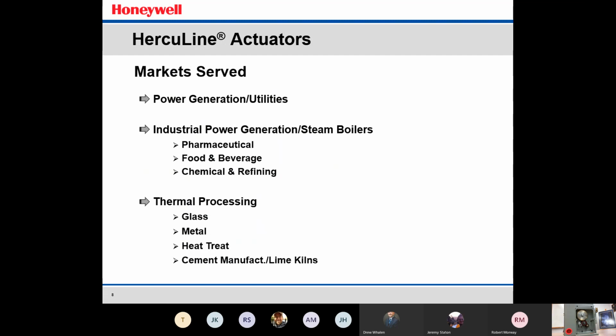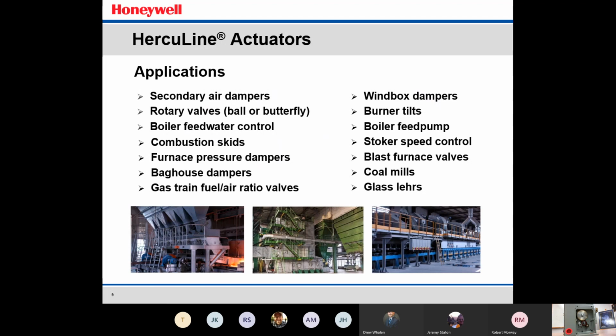Other applications inside these facilities that I mentioned on the previous slide: secondary air dampers, rotary valves, boiler feed water, combustion skids. Combustion skids are supplied to heat treat, steel, glass. In the glass industry, these 10260s are used pretty widely among a lot of the leading glass manufacturers in the U.S. So typically, if you walk into a glass plant, you'll see these on the combustion skids. Furnace pressure dampers. So this is your draft pressure control that needs very, very finite control to either the furnace or the heat treat oven, where you're controlling a draft pressure that might be down into the 0.4 to 1 inch of water column. And with that narrow of a band of control, you need a little bit more accurate actuator. And with the repositions that you get in the 10260 and the Herculine, it does really well in those applications.